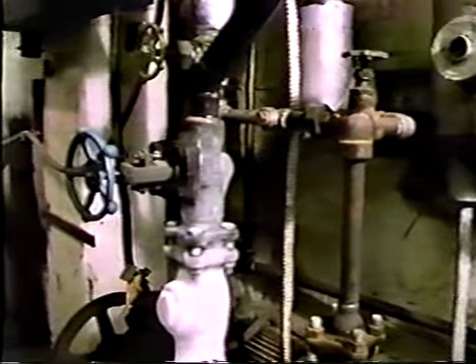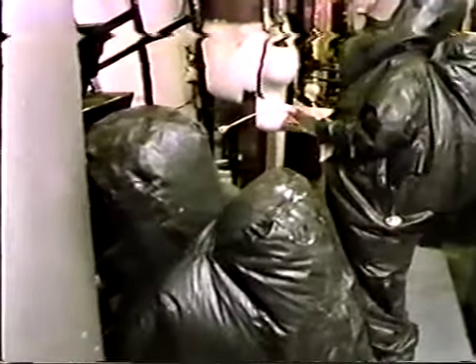Otherwise, it will be necessary to thoroughly ventilate the building. Only water fog or explosion-proof smoke ejectors should be employed. Positive pressure ventilation can be conducted without placing ejectors in the vapor. All nearby sources of ignition must be controlled. Following ventilation and before response personnel enter the building, monitoring devices should be deployed to be sure the release is not within the flammable limits. Monitoring devices include detector tubes, toxic gas detectors, and ammonia detectors. Once inside, the source of the leak must be shut down before any repairs are made. Opening or closing the wrong valve can make a dangerous situation worse.